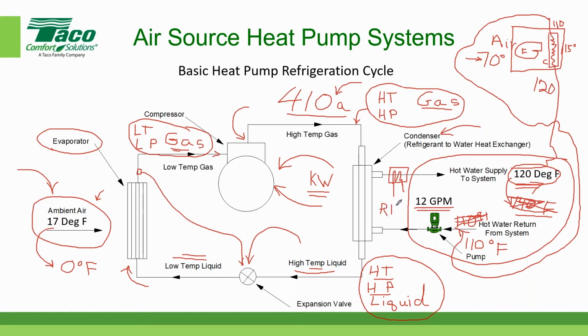Now remember, the whole goal of these new air to water heat pumps is electrification. In other words, that we're not going to heat buildings using fossil fuels. It's going to be 100% electric. So if we don't have enough capacity because of the ambient temperature being so low, we can supplement that with resistance heat. But we only need to do that a few hours out of the year because the overwhelming majority of hours will be handled by the compressor. Put a big check mark here by the compressor. So that's how you compensate for lower ambient temperatures.